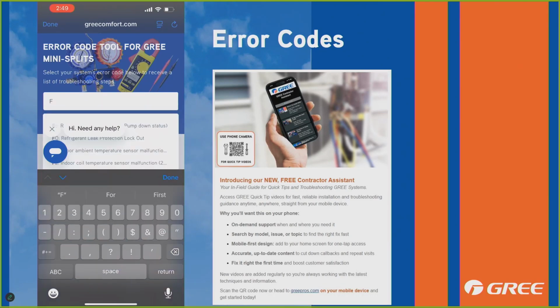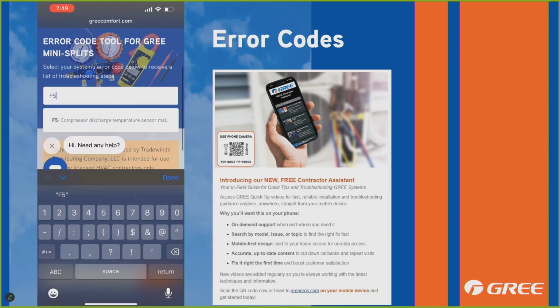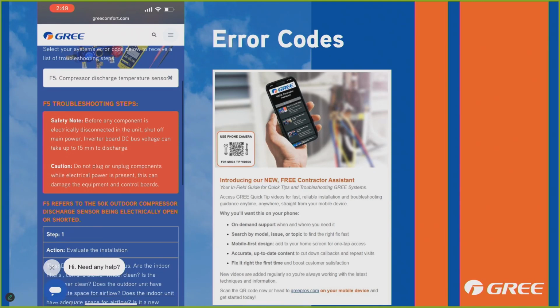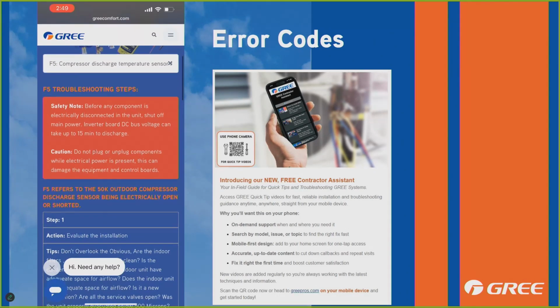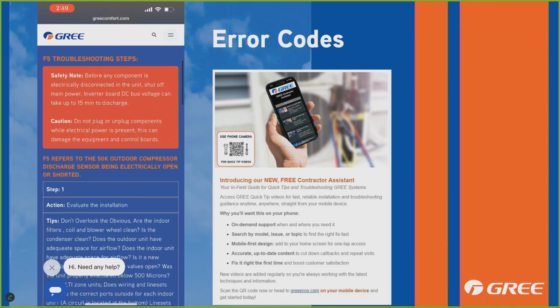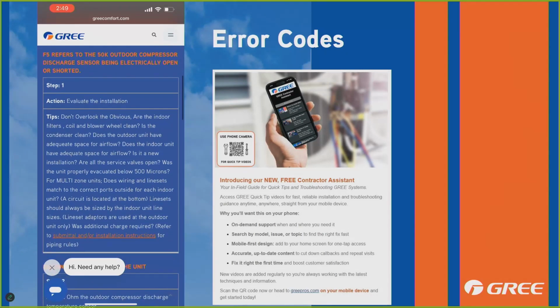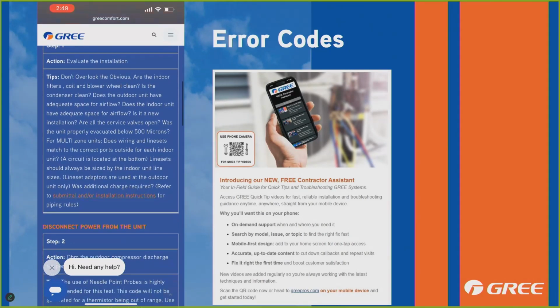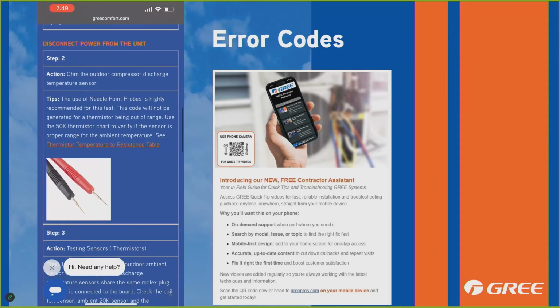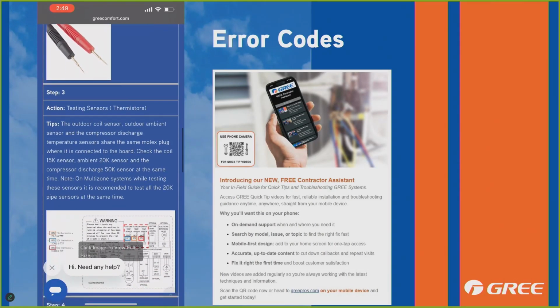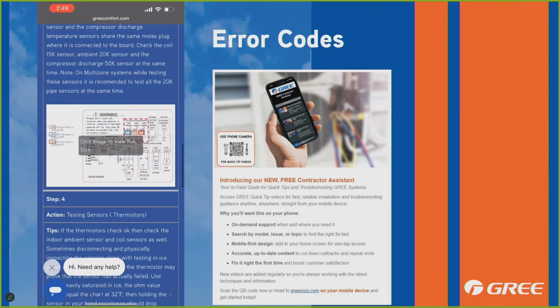In this case, you can type the error code into our troubleshooting tool. It's an F5, so we type that in, and then we've got step by step: evaluate the installation, don't overlook the obvious, that kind of thing. But what the error code itself means is that you've got a discharge temperature sensor error code.